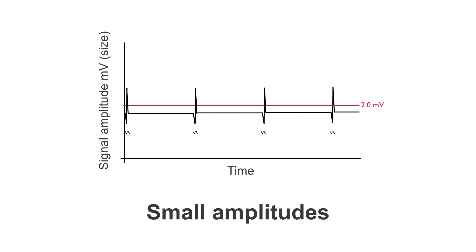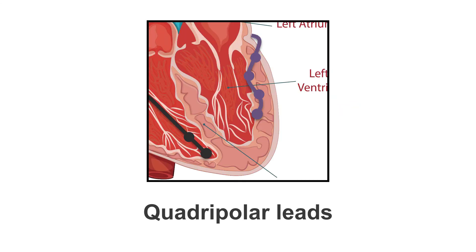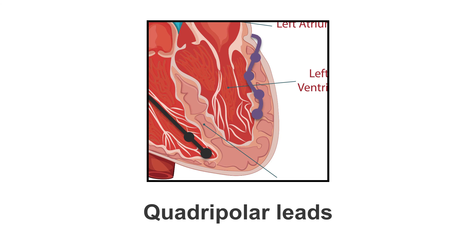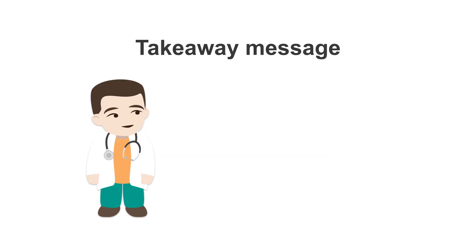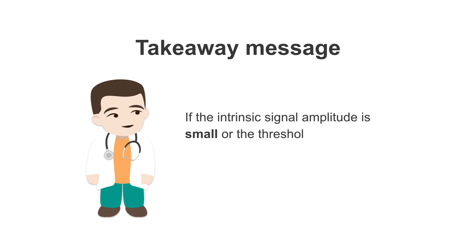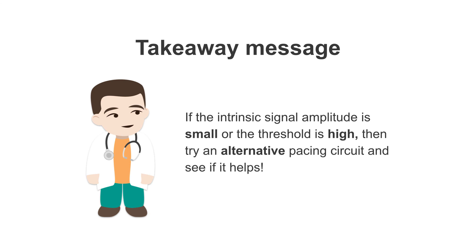If we consider a quadrupolar lead, think about all the possible options we have and all the vectors on offer — it's really incredible. A quadrupolar lead gives us a huge amount of options. So, your takeaway message: if the intrinsic signal amplitude is small or the threshold is high, then try an alternative pacing circuit and see if that helps.